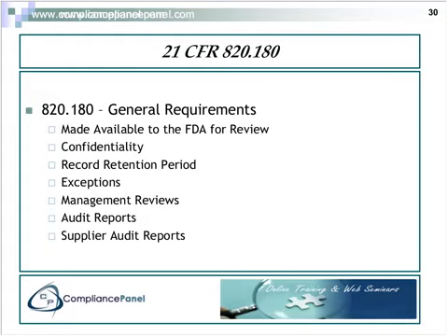There are also exceptions to what the FDA can look at when they come through. For instance, they can't look at your audit reports, your management reviews, or your supplier audits. This was done for a reason, so that they didn't have a backdoor entry. For instance, if you're buying from a supplier that is itself a medical device manufacturer, and they come in and look at your supplier audit of that facility, they don't have any information relating to that site before they go do an audit there. So this is much different from an ISO auditor, who has privy to look at all of these requirements.